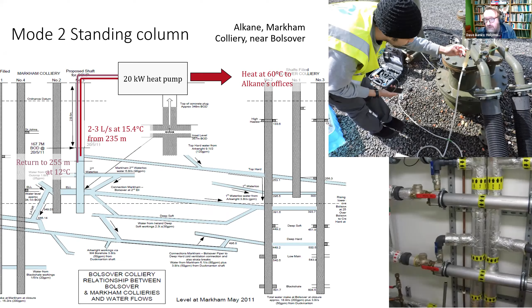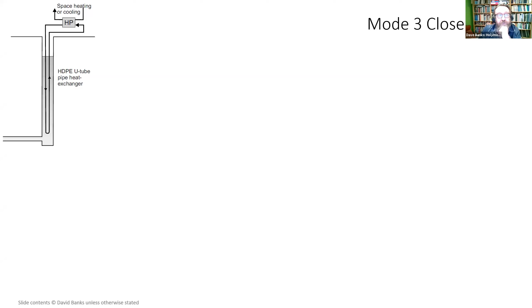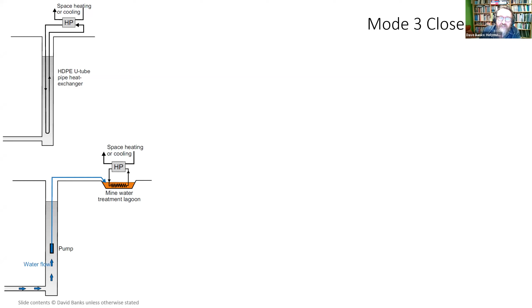The third means of getting heat out of mine water - I know we're focusing on open loop systems today, but you can actually do closed loop. There are mines in Norway where they put typical heat exchange U-tubes down mine shafts and circulate a heat transfer fluid down those to extract modest amounts of heat. Or at places like Cap House, where you have treatment lagoons, you can put the heat exchanger in the treatment lagoon and take heat out there by circulating a closed loop of heat transfer fluid around a heat exchanger.